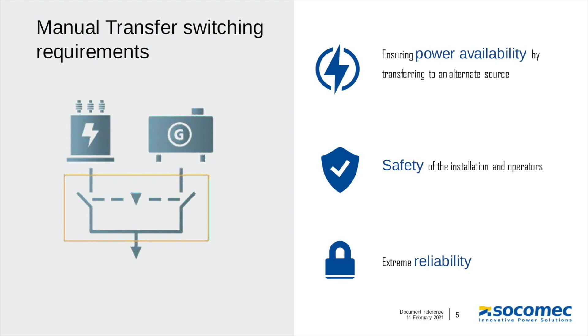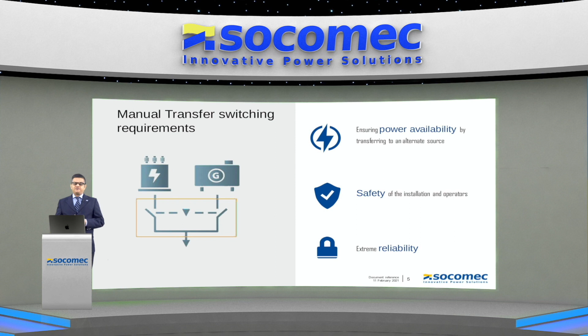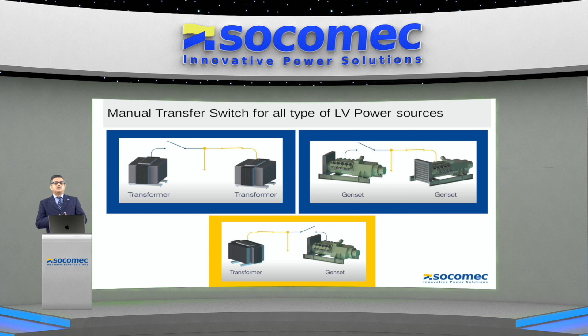Transfer switching equipment ensures power availability by transferring to an alternative source, contributes to overall safety of the installation and operating personnel, and enhances reliability. The different usage types depend on the industry application - it could be transformer to transformer transfer, or genset to genset transfer, but more commonly it's transformer as the mains and a DG set as the emergency source.